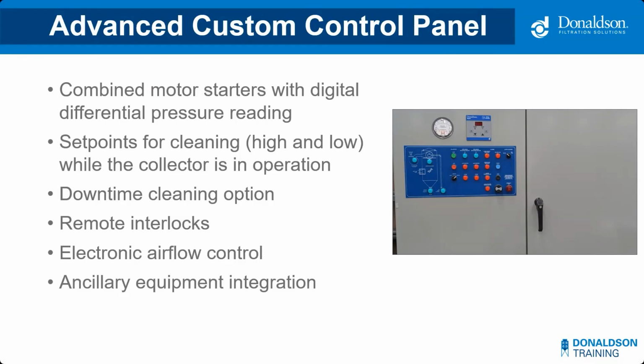In addition to everything we've discussed so far as a feature of a control panel, an advanced custom control panel will typically allow for remote interlocks and the integration of even more ancillary equipment. Interlocks are very common and are set up so the dust or mist collector will turn on or off with a different machine. We most commonly see these with CNC or machining operations where the collector only needs to be running when the CNC is cutting.